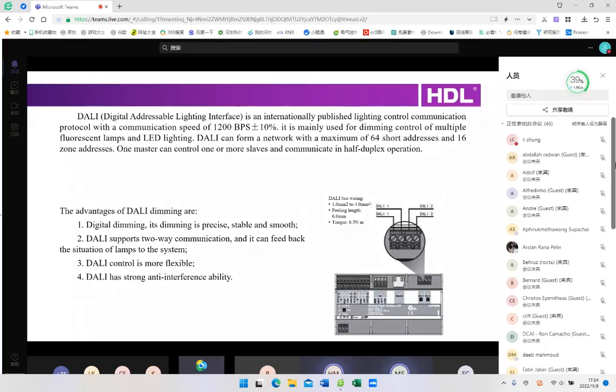For example, why we add this function is because a DALI module controls different lights from different rooms. Then how can a DALI module control 2 regions? You have to divide them into different regions, then you can use a sync to control the all-on and all-off of the lights in the room. So we enable the DALI module to be able to divide zones for different rooms, and one master can control 1 or more slaves and communicate in half duplex operation.